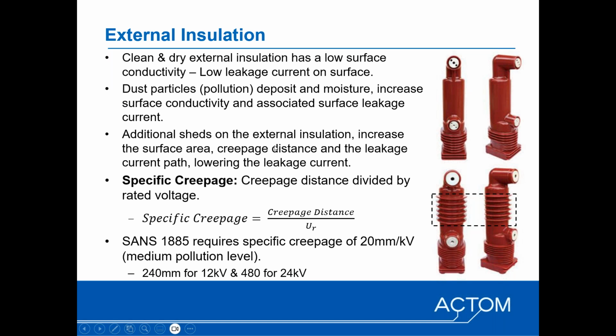By adding additional sheds on the surface, as shown there in the image here, you're basically increasing the surface area of the surface, you're increasing the creepage distance, and the leakage current path, effectively lowering the leakage current that will flow over the surface. Now, the specific creepage is defined as the creepage distance divided by the rated voltage, and in terms of SANS 1885, which requires a preferred specific creepage distance of 20 millimeters per kV, the actual creepage distance for a 12 kV system should be 240 millimeters, and for 24 kV 480 millimeters when you measure it.